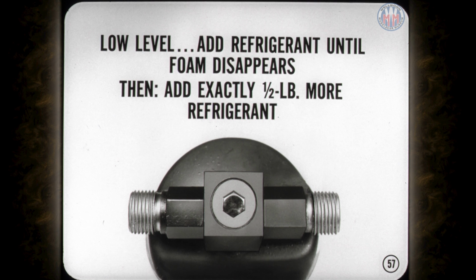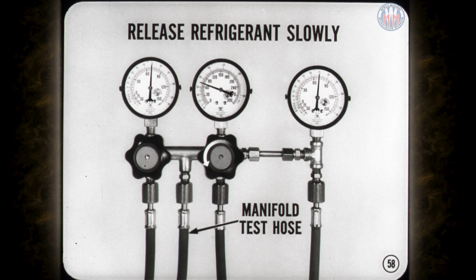Adjust the suction gauge valve to meter the inward flow of refrigerant so the gauge reading does not go above 50 pounds. When the level is high, you first release refrigerant slowly through the manifold test hose until foam starts to appear in the sight glass. Then you connect the refrigerant source, purge the manifold hose, and again add exactly 1/2 pound of refrigerant.